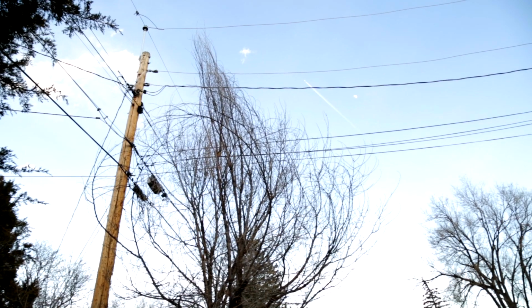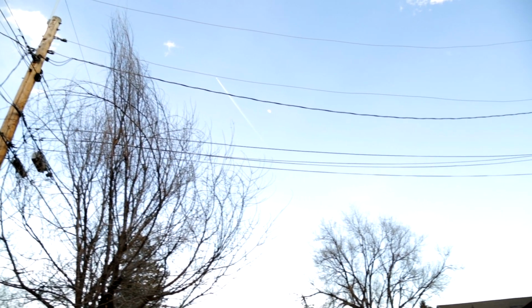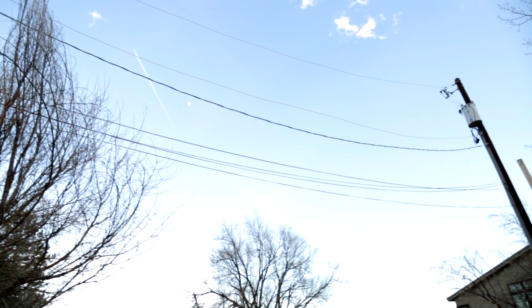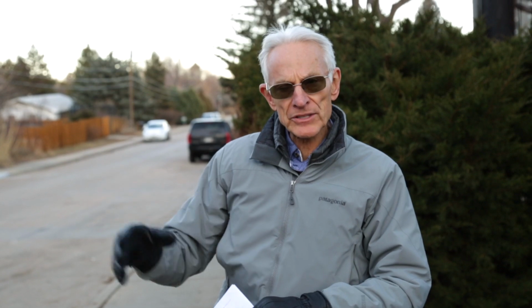So we have a condition in elevated or above ground distribution systems that we talked about when we were looking at the below ground distribution system, or the buried distribution system. And that's where there can be an unequal current flow on the supply wire versus the return wire. That's a condition caused by the power company. We won't get into why it happens. It doesn't have to happen, but it does sometimes. When that happens, there is this large field around the wires, and it'll affect the houses along the street.